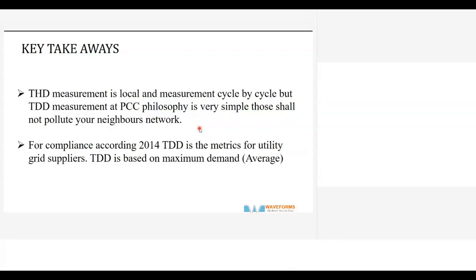See, the philosophy is very simple: you are not supposed to pollute your neighbor's network. Okay? You can have as much harmonics inside your plant, no issue, but the utility will measure the harmonics at the PCC, and that is called TDD. So you have the freedom, you can swing your arms, but your freedom ends where the other man's freedom begins. So that's again philosophy. You should not export your harmonics to others.